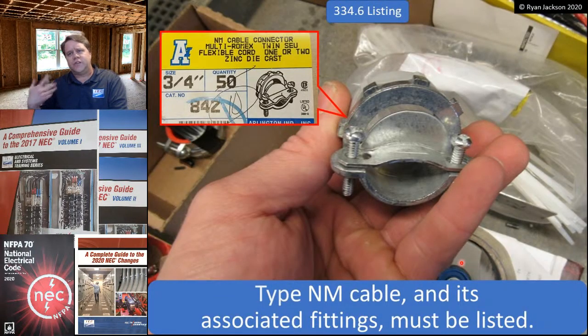So, associated fittings would include cable clamps like this. That would be a fitting for NM cable. I want to point out that support hardware is not a fitting. Support hardware is support hardware, and it's regulated in 334.30, and we'll talk about it. But support hardware, generally speaking, does not need to be listed. Only the cable fittings need to be listed. Now, you can go to Article 100 and read the definition of fitting, and some of you might say, Ryan, cable ties, staples, they might be fittings. I get it. That's not the intent. There are proposals in the 2020 to clarify that, and I hope it gets changed in the 2023. But for right now, the cable and the associated fittings have to be listed.